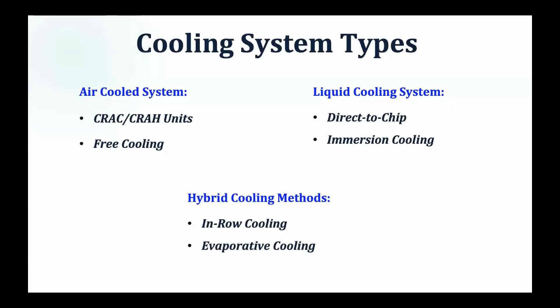Hybrid cooling system is a combination of liquid and air cooling, where chilled liquid is supplied to a heat exchanger at the server rack level, and the air circulating inside that rack is cooled. That's why it's called hybrid cooling. Evaporative cooling is also a hybrid cooling system, where water is used to cool the air, sometimes coming in direct contact with the water, sometimes not directly in contact. In further slides I'll explain direct and indirect evaporative cooling.